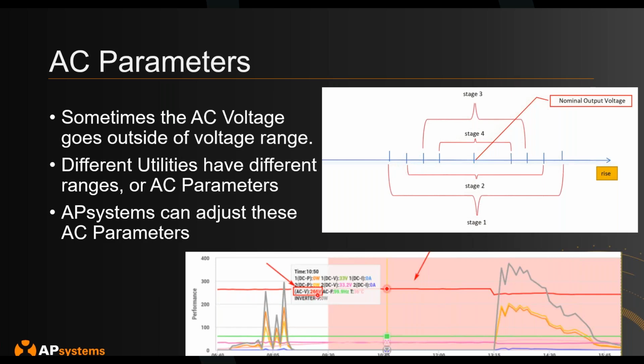For example, over here, you'll notice a microinverter hitting like 266 volts, either because of voltage rise effects from the wiring or from other things. Maybe you're at the end of the line of the utility, so the grid is a lot more unstable. A lot of times if it exceeds that voltage or operates outside the ranges we set, it will turn itself off just to keep within its own self-programmed safety limits.